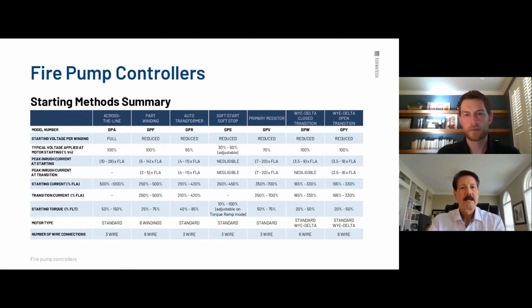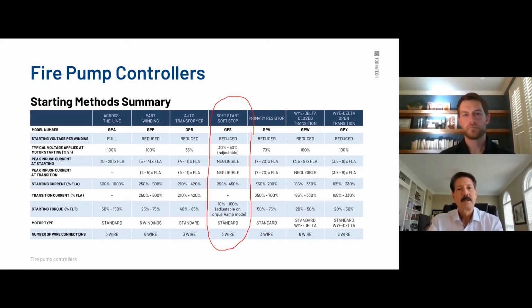Soft start. That has been around for a long time. I mean, a long time. Electronic equipment tended to be very, very sensitive to temperature and vibration. But through decades of improvement, whether it be any type of electronic equipment, but primarily into starting motors, it's improved. So it's become very efficient. There's some flexibility there. If you ever need to tweak it, you do have a few adjustments, and that's a rare case, but sometimes it can correct minor inefficiencies in the design of a system. And again, it takes 3 wires. This is quite nice.